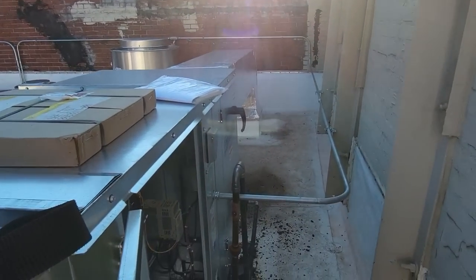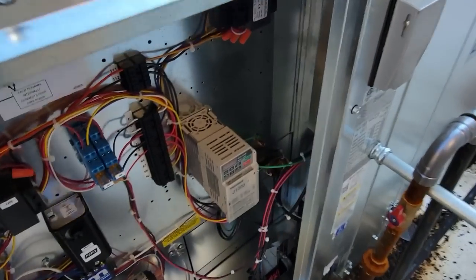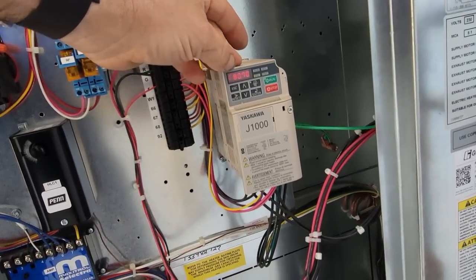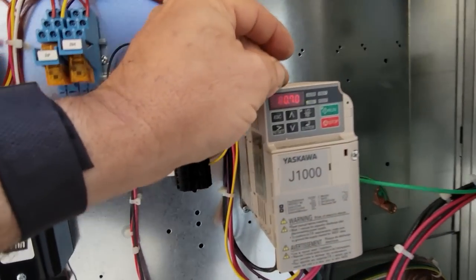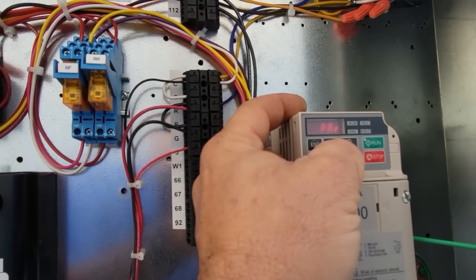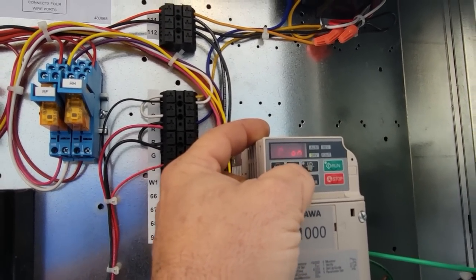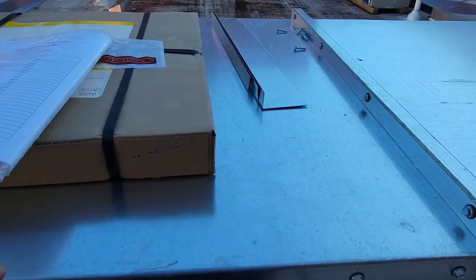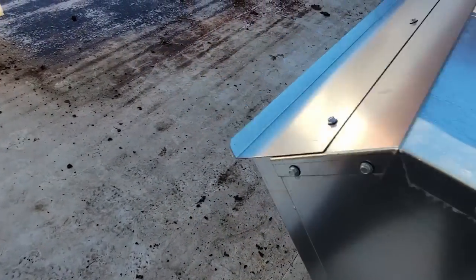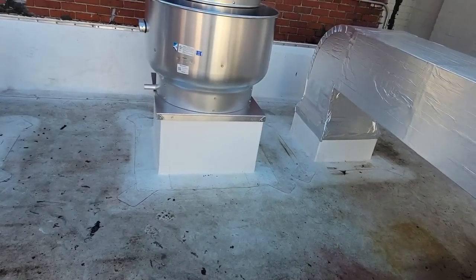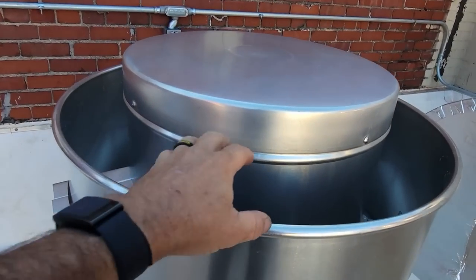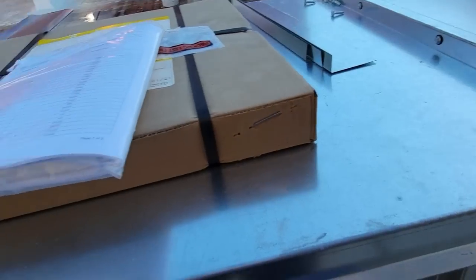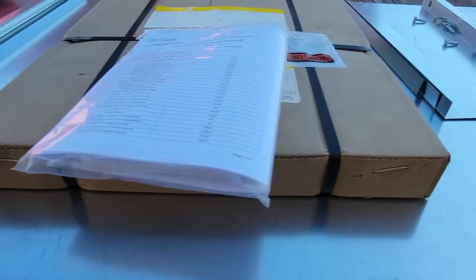Hey, they were able to turn it on for me down below. Got an inspection here this morning. Frequency 80 hertz is what it looks like. Parameter setup, blah, blah, blah. Yeah, it's hauling ass. We ain't gonna mess with a lot of that. They just want to make it run and pass inspection, and then they can fine tune it later. So we got the exhaust running. It's hauling ass. We're gonna have to set up the dampers most likely on this, which we can get to from the other side.